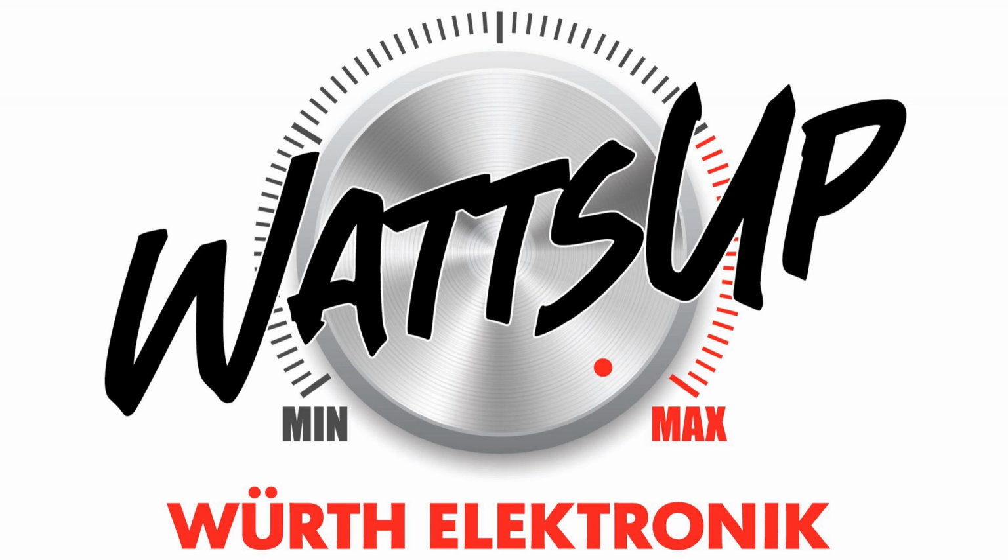If we need higher or want to have higher permeability values, then we have to use manganese zinc mixtures, where it goes up to 10,000 as a factor. And the highest values we can reach with nanocrystalline material, here we have a maximum of 95,000, but in general you can get materials up to 200,000 as a factor. But those are for specific applications.